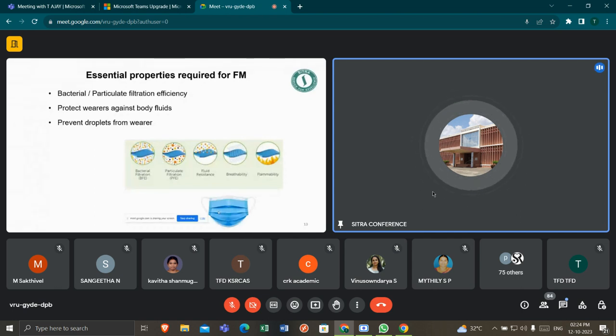If you are testing for a very minimal type of face mask like a class 1 face mask, we have to check for the breathability of the mask and also the bacterial filtration efficiency. The breathable efficiency of the wearer has to be maintained. The differential pressure of the breath outside and inside has to be maintained by the mask. It should not restrict the breath, because oxygen requirement is also very important. And bacterial filtration efficiency, so it has to filter bacteria coming through it. These are the two important aspects for the class 1, very minimal type of mask. It should at least possess bacterial filtration efficiency and breathability.